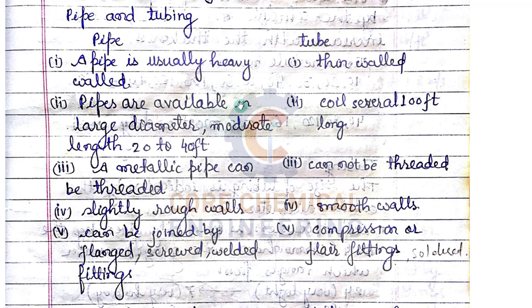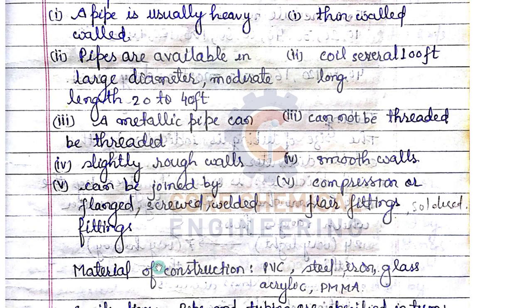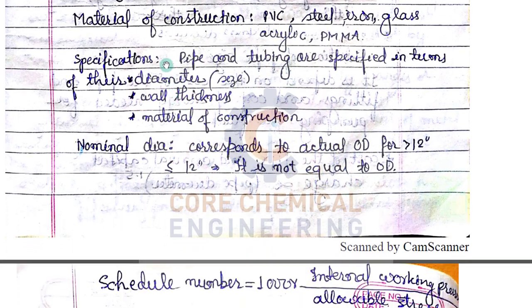Tubes are basically thin-walled and can be coiled up to 100 feet long. Tubes cannot be threaded, have smooth walls, and can be joined by compression or flare fittings. Materials of construction for pipes and tubing include PVC, steel, iron, glass, acrylic, or PMMA. Pipes and tubings are specified in terms of diameter, wall thickness, and material of construction.